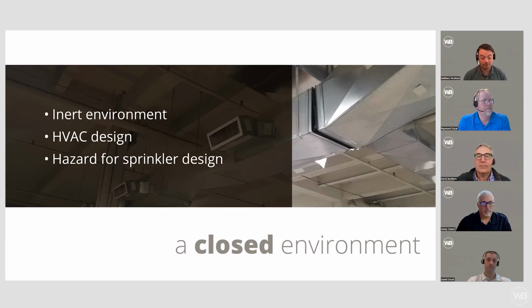As far as sprinkler design, the sprinklers still need to be designed toward the proper hazard. They'll need correct spacing and correct flow requirements. One other thing to mention is that in any areas with high temperature, you might need to put high temperature sprinkler heads throughout the space.